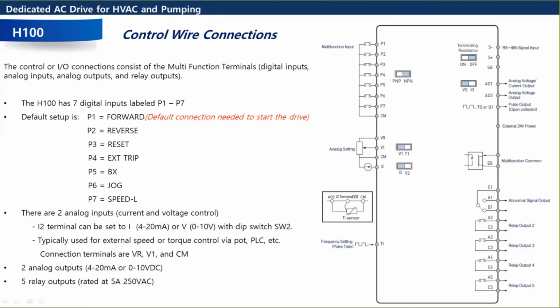So we have AO1, AO2, which is our analog outputs. We have the S plus and S minus. That's your communications, which you would use for the BACnet, the Modbus, whatever you select in the drive. And then this drive has the most relay outputs. So it has 5 relay outputs. And if you look closely on that bottom line, they're all rated at 5 amps, 250 volts. So this drive has the most robust, highest amperage rated relays out of all of our drives.